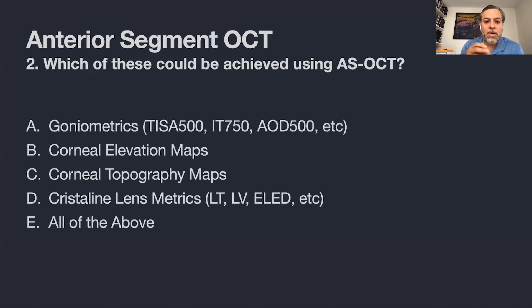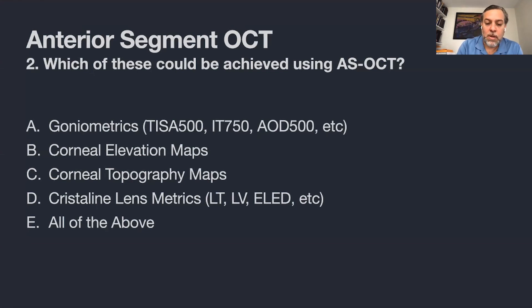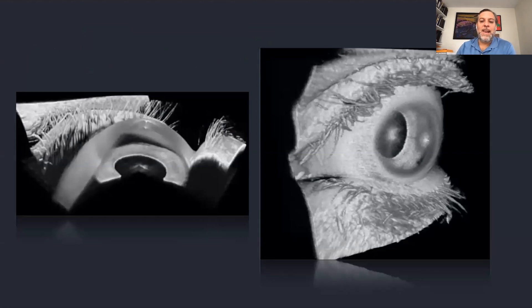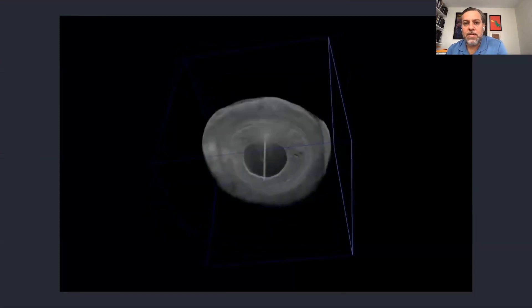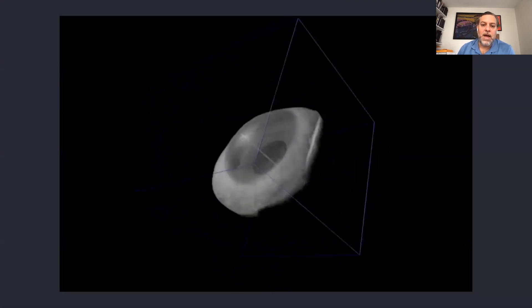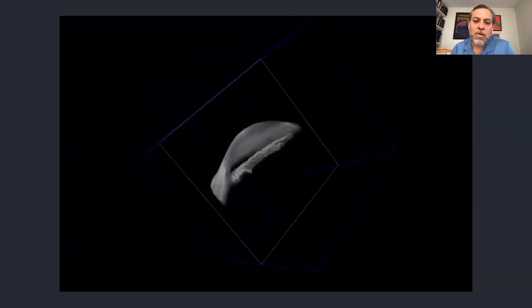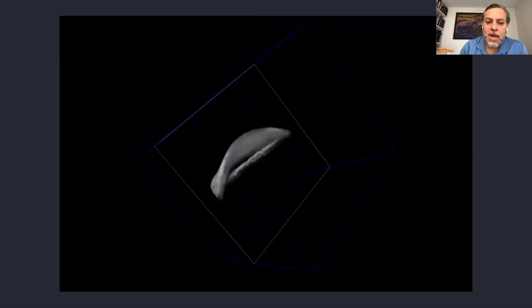With swept source OCT you get better lens metrics than with other machines. Biometers like the IOLMaster with swept source technology get excellent measurements of the crystalline lens and even the whole eye. The technology can now do 3D reconstructions of the anterior segment — instead of 10–16 scans, swept source OCT performs hundreds of scans enabling complete 3D anterior segment reconstruction with cuts in different positions.